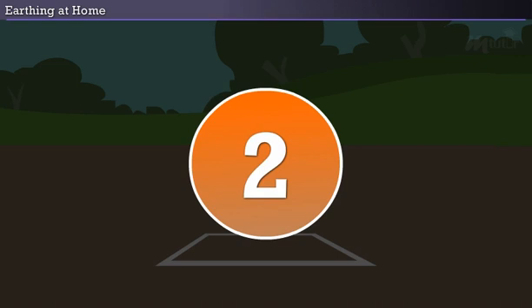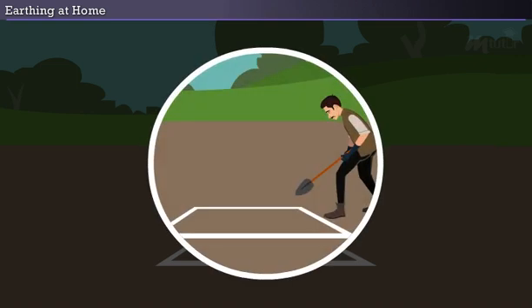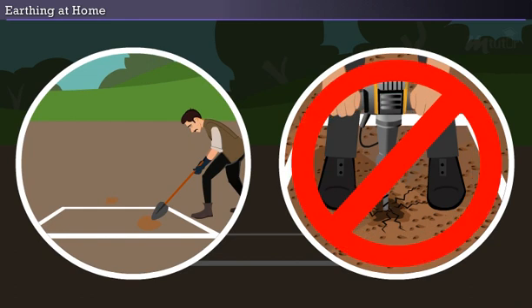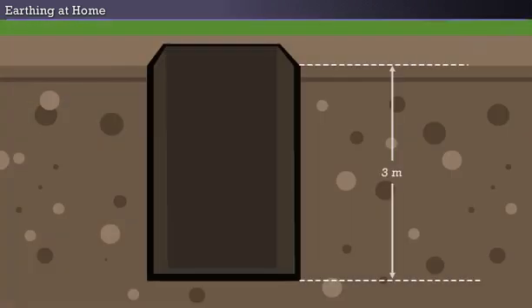Step 2: If the place is soft, use a shovel to dig the pit. But if it is rocky, use a land driller. But it is better to avoid rocky places. Dig the earth for up to 3 meters depth and its length and breadth of 1.5 meters each.